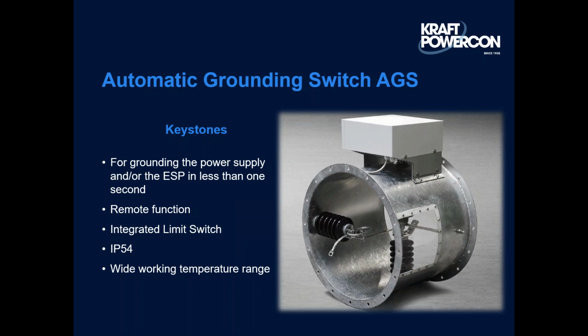At many facilities, when they know combustibles may be getting to the precipitator, all they do is turn off the power to the controller. The difficulty is there's still a static charge within the precipitator - it's a giant capacitor. The density of the gas may change so the spark level lowers. So as combustibles enter, there's still potential for a spark, it sparks, and we have an explosion.